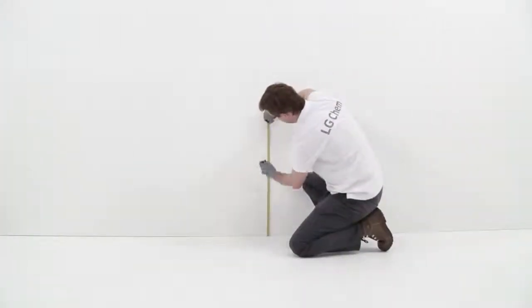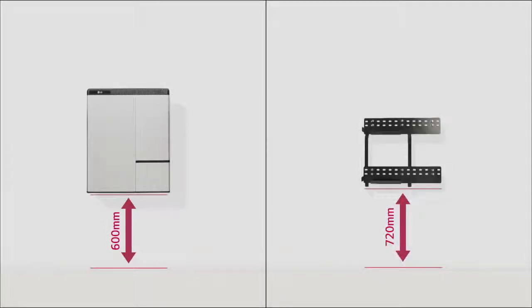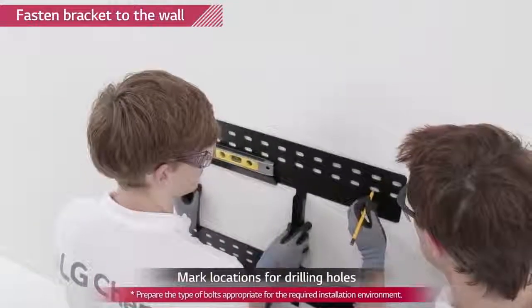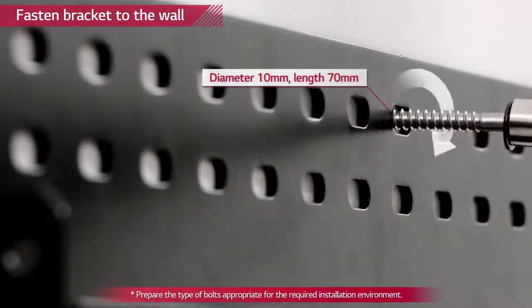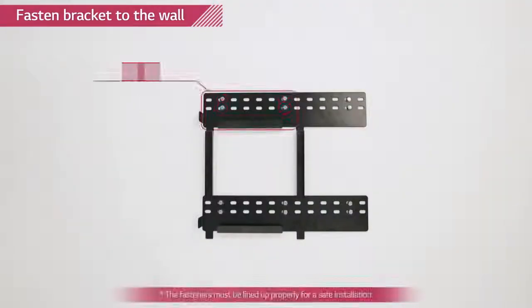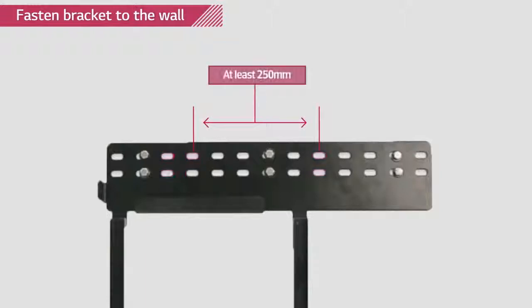First, the wall mounting bracket needs to be fixed. Please note that the RESU 7H and RESU 10H can only be wall mounted. For wall mounting bracket installation, make sure you have at least 720 millimeters above the ground. Mark the location on the wall by placing the bracket to the wall, and then drill anchor screws to the wall. Use at least 4 bolts for area 1 and 3, and at least 2 bolts for area 2 and 4. The distance between bolts in area 1 and 2, and 3 and 4, must be at least 250 millimeters. The wall mount bracket must be leveled.